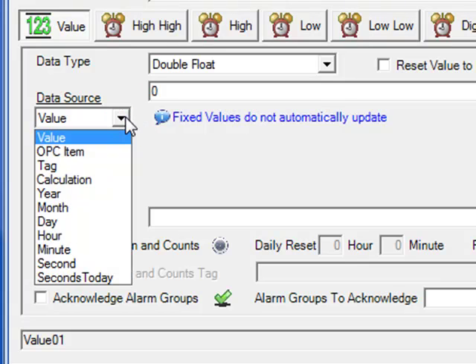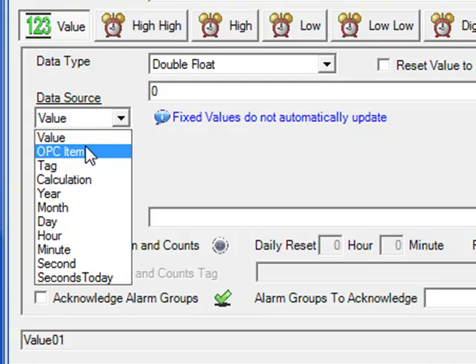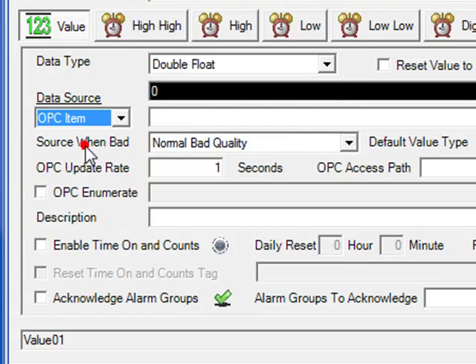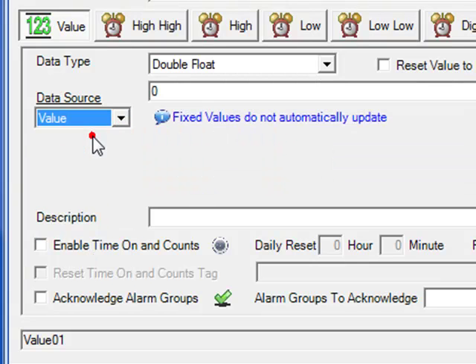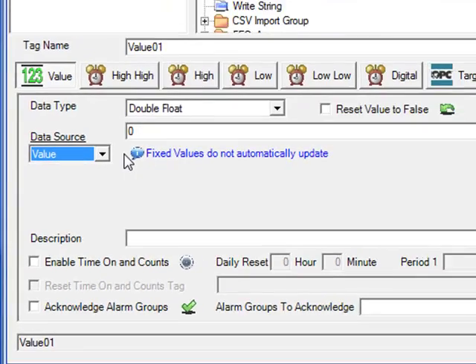If you want to have the values written to an OPC server, you would set OPC item as the data source, and then browse for the OPC item that you want to set the data to. In this way, when a write occurs to an OPC systems.net tag, the value will go down to the OPC item defined in the OPC server.